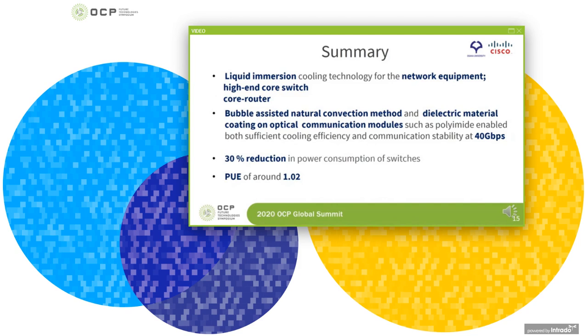So far, I have demonstrated the effectiveness of liquid immersion technology. It exhibits high potential for cooling both servers and network equipment. The bubble-assisted natural convection method along with dielectric material coating of the wiring surface enabled both sufficient cooling and communication stability at 40 gigabit per second. As a result, power consumption of switches was reduced by 30% while achieving a PUE of 1.02.